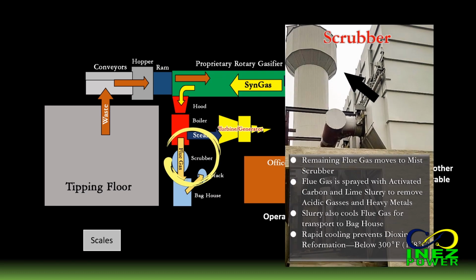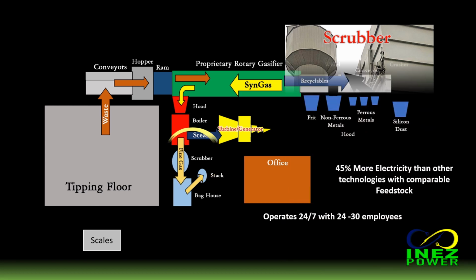The flue gas exiting the boiler is directed to the air pollution control unit, consisting of a spray dryer and a baghouse. In the spray dryer absorber, the off gases are treated to remove any remaining acids and metals that might be present. A slurry of lime and activated carbon is injected into the top of the spray dryer absorber unit for treatment. Spent carbon and other particulate matter generated at the spray dryer absorber are collected at the bottom and transferred via conveyor to a fly ash bin.